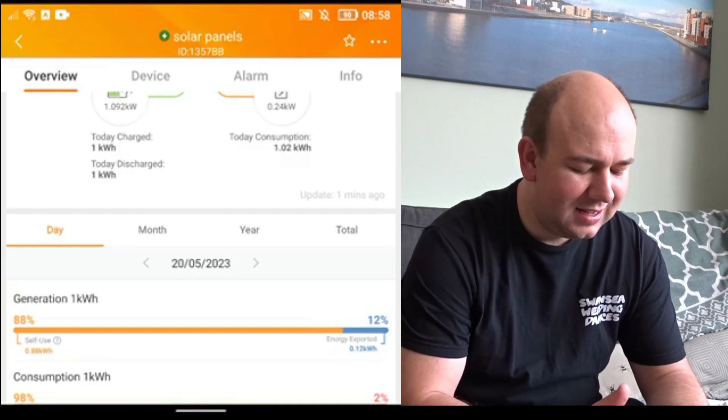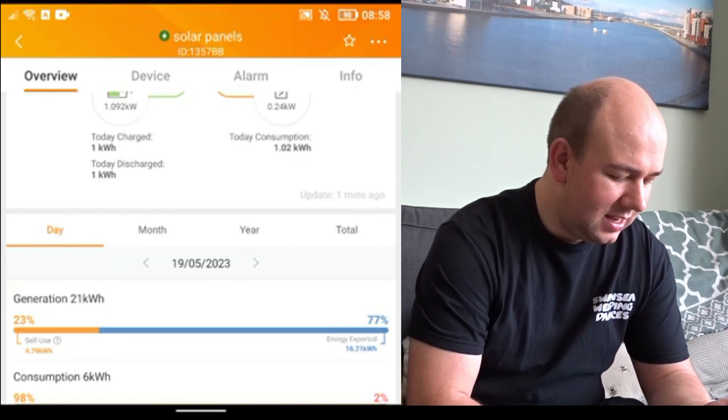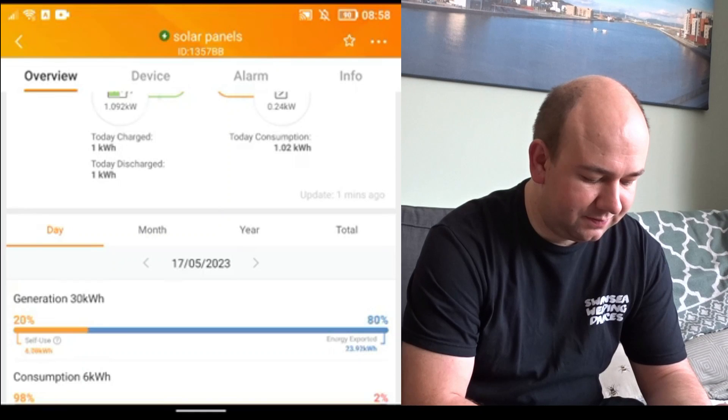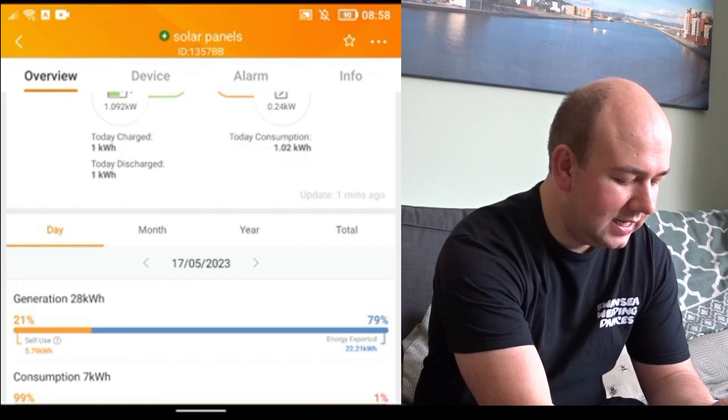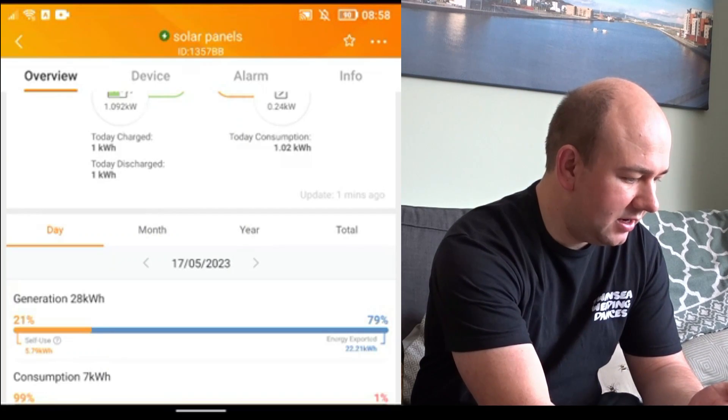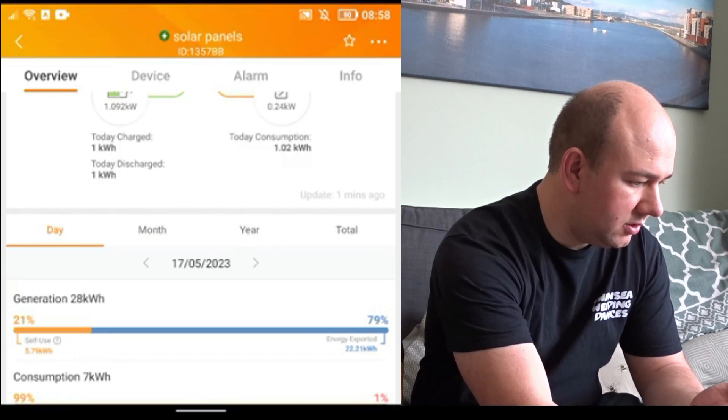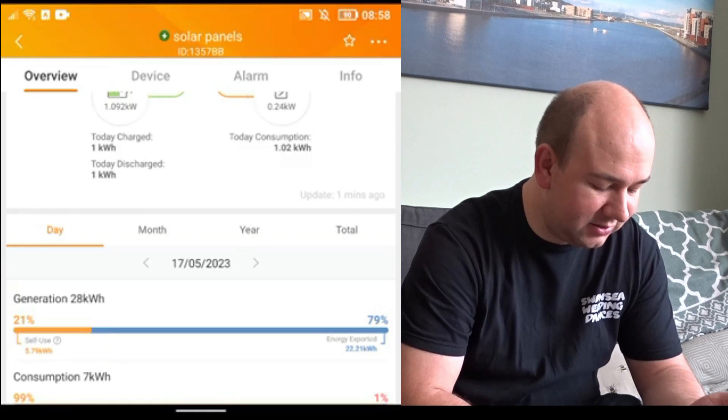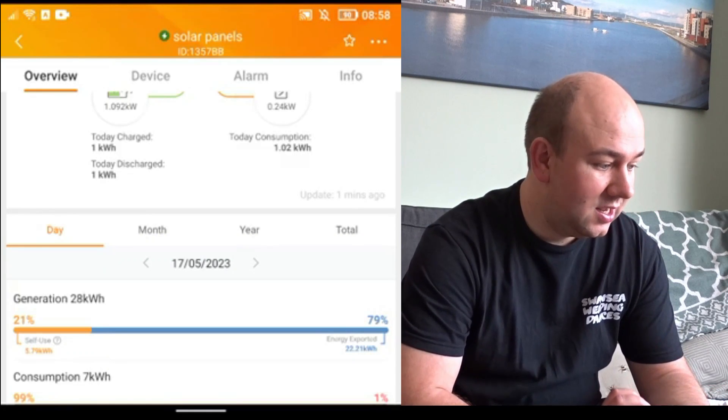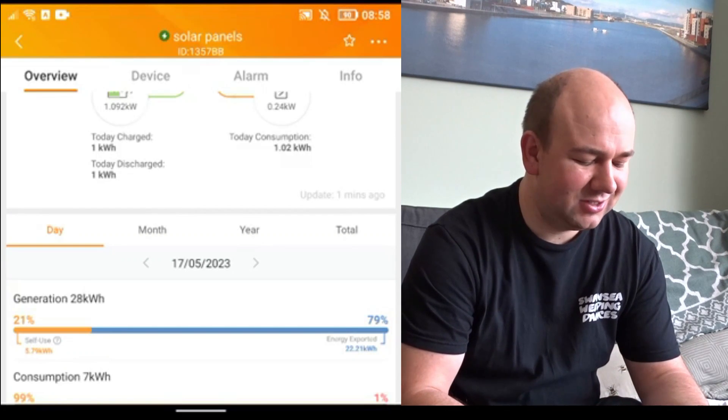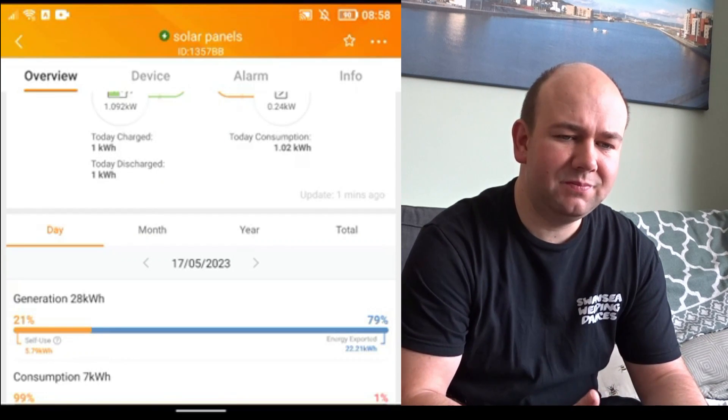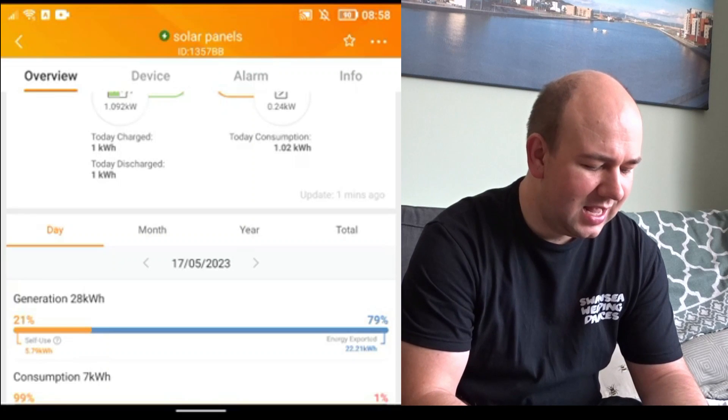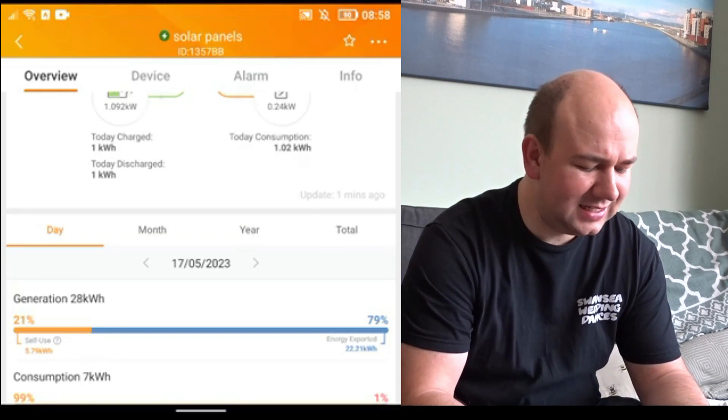So if I go back a previous day, generation of 21 kilowatt hours, 30 kilowatt hours, 28 kilowatt hours. So on the 27th, I'm just looking through my spreadsheet, I actually generated 27.4 kilowatt hours. So they've rounded up, I've nearly gained an extra over half a kilowatt hour. Again, it's not a massive deal breaker, but over the course of a year that does mount up and throw out your data. And it's a very easy fix.